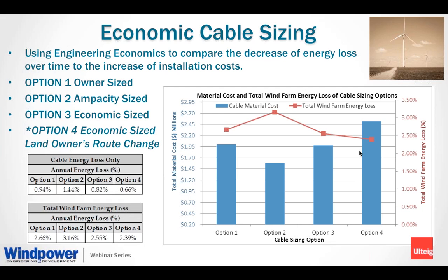And this slide shows there are 4 different options that were looked at. Options 1, 2, and 3 show a collector system of buried underground 34.5 collection cable that was all laid in the same row, so it's the same trench. The only differences between options 1, 2, and 3 are the number of turbines on a particular size cable. The owner had his own scheme that he wanted. We sized the absolute minimum size cable that you could possibly use for the number of turbines on each one. And then we started upsizing the cables that have a tremendous amount of loss on them, which we would call the economic cable size. And option 4, just to show comparison, was where the landowner had a route change because he didn't like the cable in his yard.